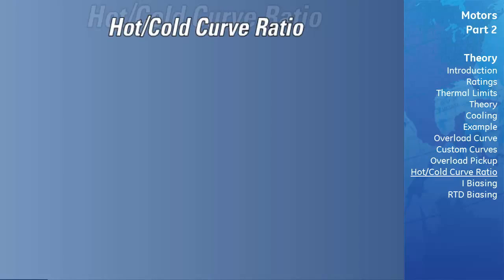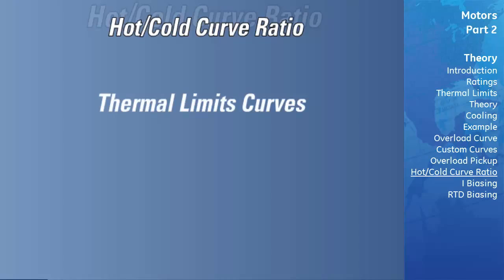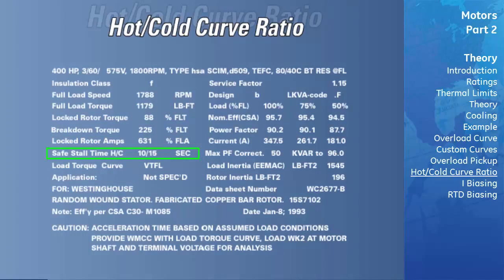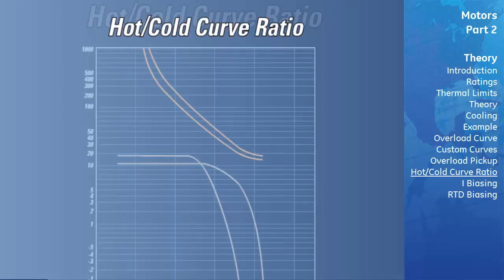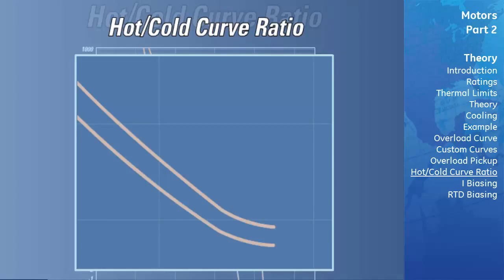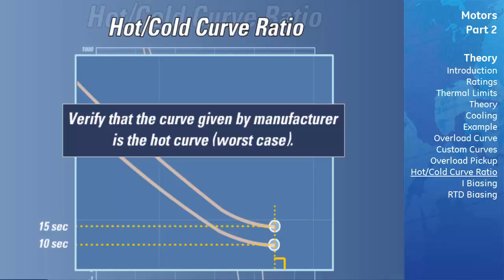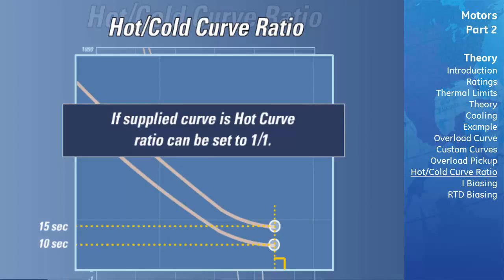Determining the Hot-Cold Curve Ratio. The hot-cold curve ratio can be determined from either the thermal limits curves, if provided, or from the hot and cold safe stall times. If hot and cold safe stall times are used, simply divide the hot safe stall time by the cold safe stall time. If the thermal limits curves are used, run a line perpendicular to the current axis that intersects the hot and cold curves at the stall point, draw a line from each intersection to the time axis, and record the corresponding times — in this case 10 and 15 seconds respectively. The hot-cold ratio equals 10 divided by 15, which equals 0.67. If only one curve is given, verify with the manufacturer that it is the hot curve; if so, the hot-cold ratio can be set to 1 to 1.